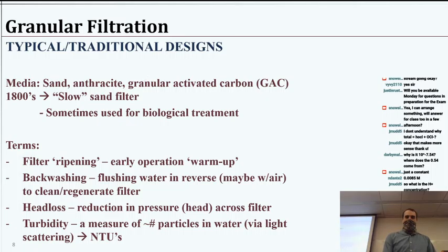Okay, a few terms to understand the operation, and I'll draw some schematics for you about these in a minute. So filter ripening, that's the early stage of operation after being washed or after being installed new. This is kind of a warm-up step where, as I mentioned earlier, once you start having some particles accumulate onto the surface, then you end up capturing more and more particles. So some of the ripening is just that, allowing an initial few particles to get set. Some of it's also the sand itself shaking back down into place, and maybe air bubbles that got left in there being flushed out, getting it settled to a point where we've got consistent pores.